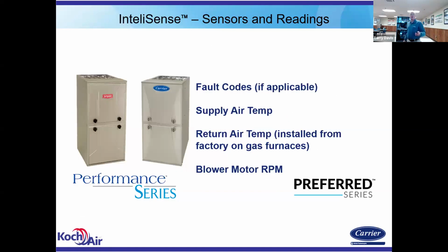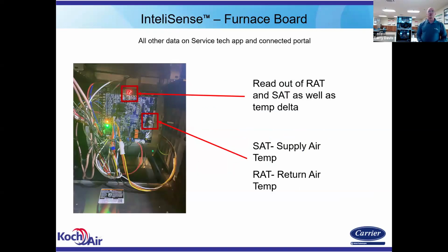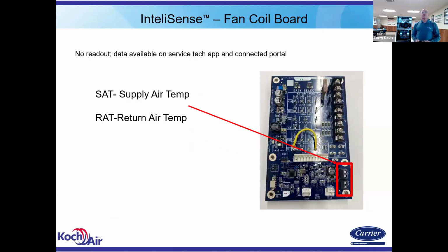Oh, and blower RPM. So it's going to tell you how hard that blower is working to move the air. On the furnaces, it'll also display it on the LCD, if you can turn that off if you want to, but it will display the temperature in there as well. On the fan coils, you get a supply and return air. There's no display on the fan coil boards, so there's no readout there, but you do get the supply and return air temperatures.